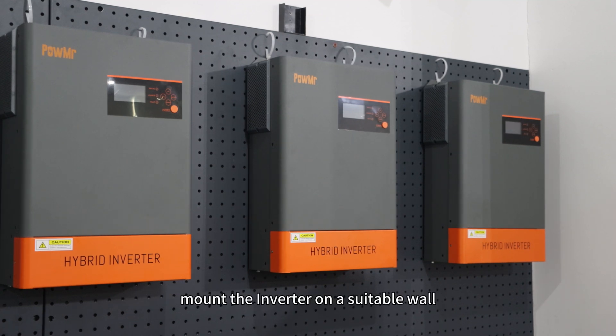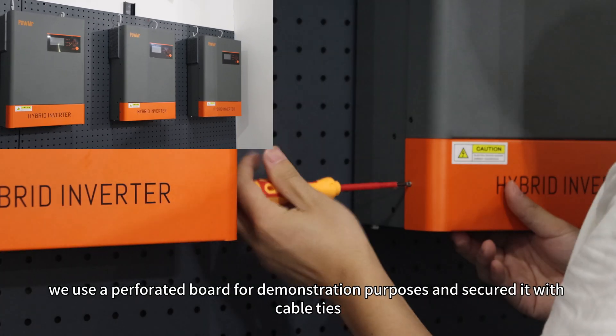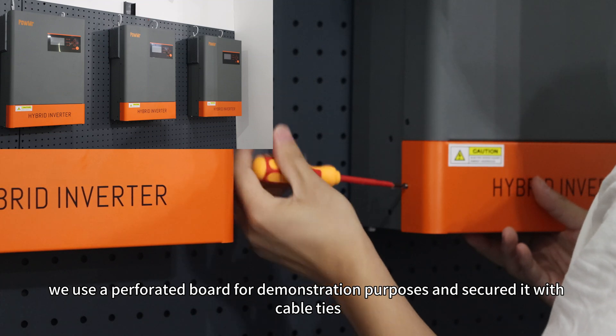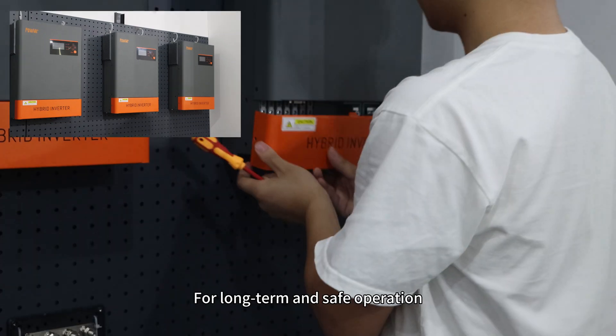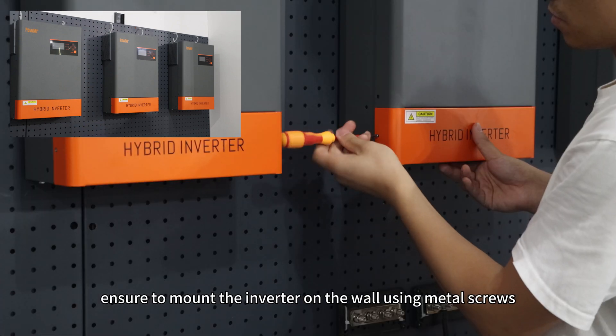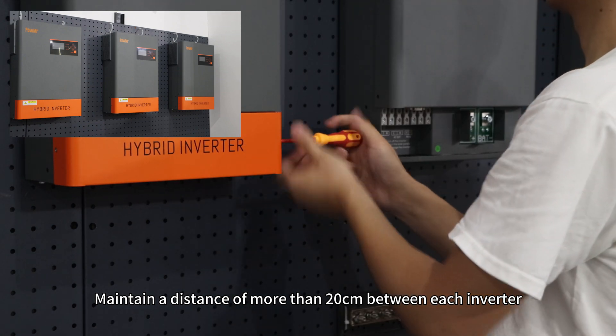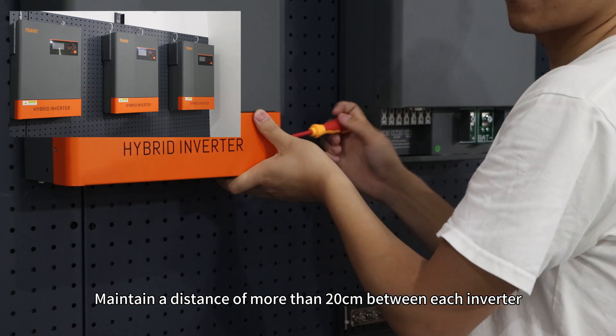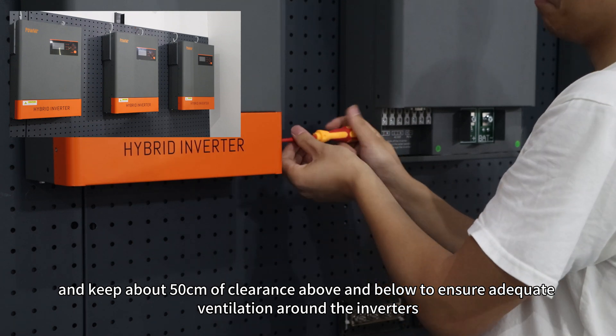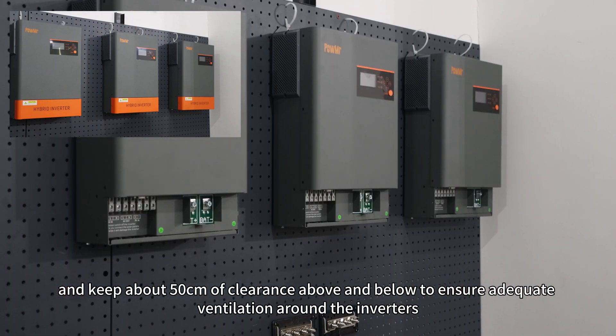First, mount the inverter on a suitable wall. Here we use a perforated board for demonstration purposes and secure it with a cable tie. For long-term and safe operation, ensure to mount the inverter on a wall using metal brackets. Maintain a distance of more than 20cm between each inverter and keep about 50cm of clearance above and below to ensure adequate ventilation around the inverters.